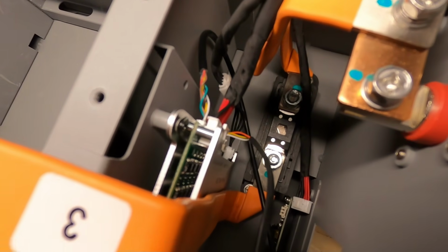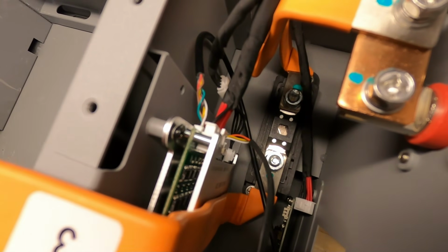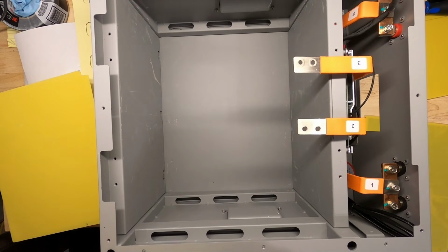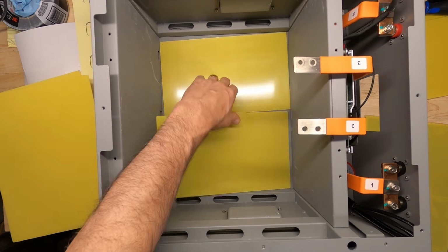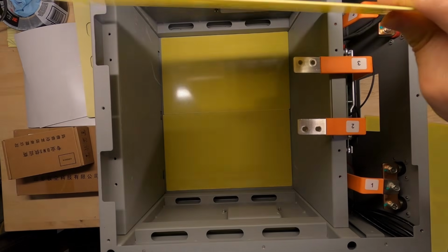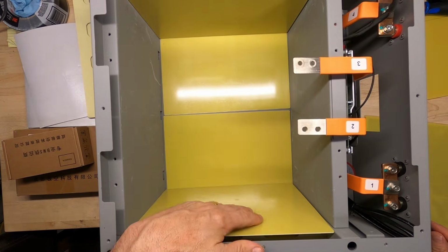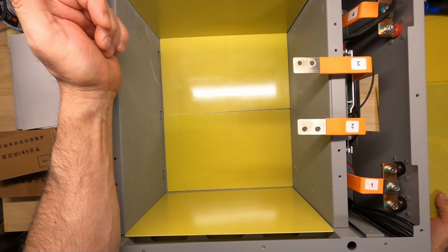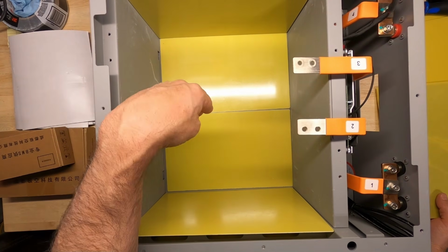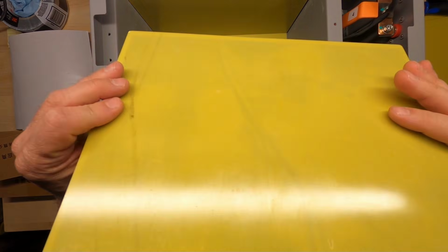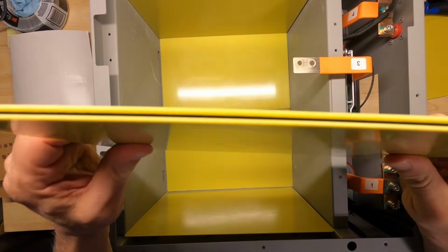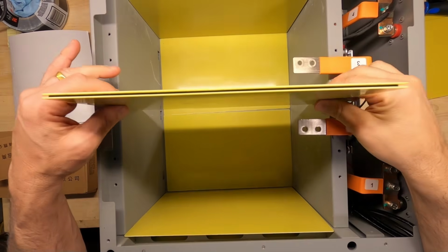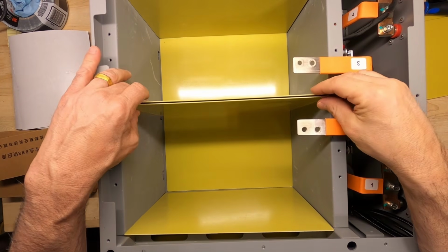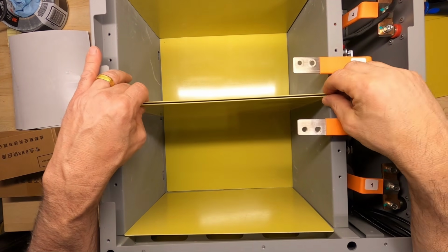Well, now I'm paranoid. I'm gonna have to check the torque on those M8 bolts for the fuse. So the 14mm nuts on the fuse were torqued to 8 Newton meters. Okay, first we'll put in the bottom epoxy board. Now the side pieces. So you'll notice, unlike the other boxes, there was no fixed metal divider plate. Instead, they gave us this epoxy board sandwich with the EVA tape in the middle. It goes like that, but we're going to need to put some cells in to hold it up.